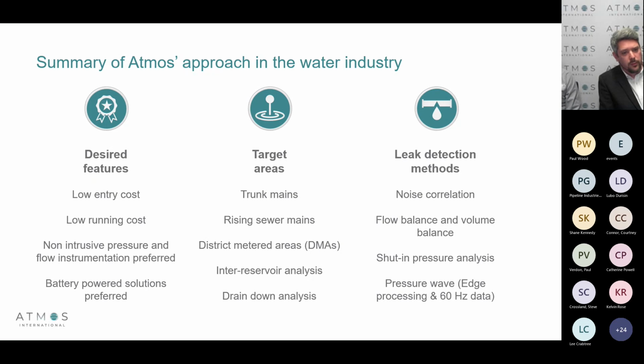Non-intrusive pressure and flow instrumentation is the preference because of the comms issues in much of the water sector, where the comms just isn't there. Improving the retrofitability aspect means that if you can have non-intrusive pressure and flow, you're much more likely to adopt this system on a network scale. Likewise, where there's a lack of power, having battery-powered solutions so you can deploy instrumentation anywhere along the network gives you a real advantage and opens up the possibility of where along the network you can undertake effective leak detection.